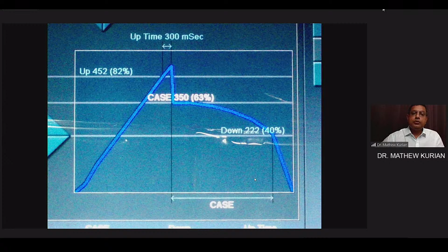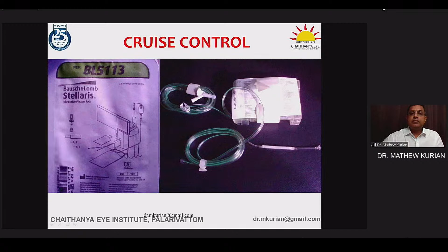Cruise control by Bausch & Lomb was the presence of a small chamber, like in a blood transfusion tube, where there's a sieve which collects the lens fragments. This prevents the nuclear fragments from clogging any portion of the aspiration line beyond the phaco tip, and prevents the fluid management system, the cassette itself, from getting clogged.